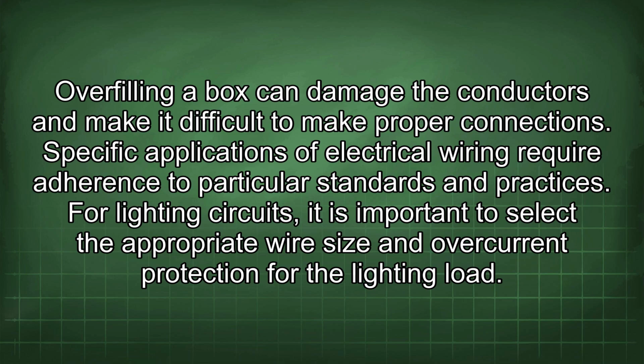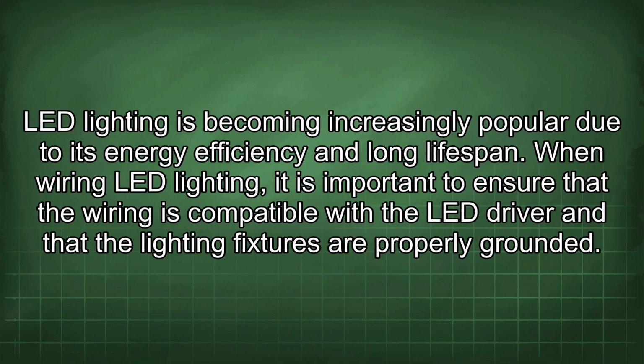Specific applications of electrical wiring require adherence to particular standards and practices. For lighting circuits, it is important to select the appropriate wire size and overcurrent protection for the lighting load. LED lighting is becoming increasingly popular due to its energy efficiency and long lifespan. When wiring LED lighting, it is important to ensure that the wiring is compatible with the LED driver and that the lighting fixtures are properly grounded.